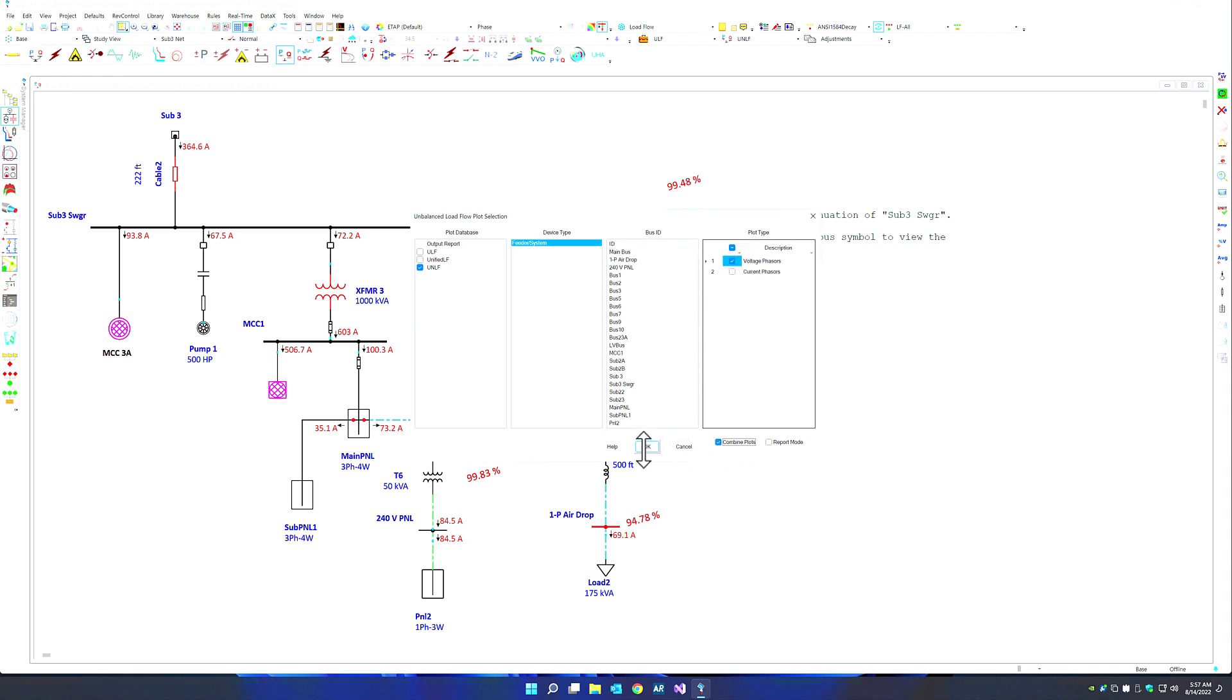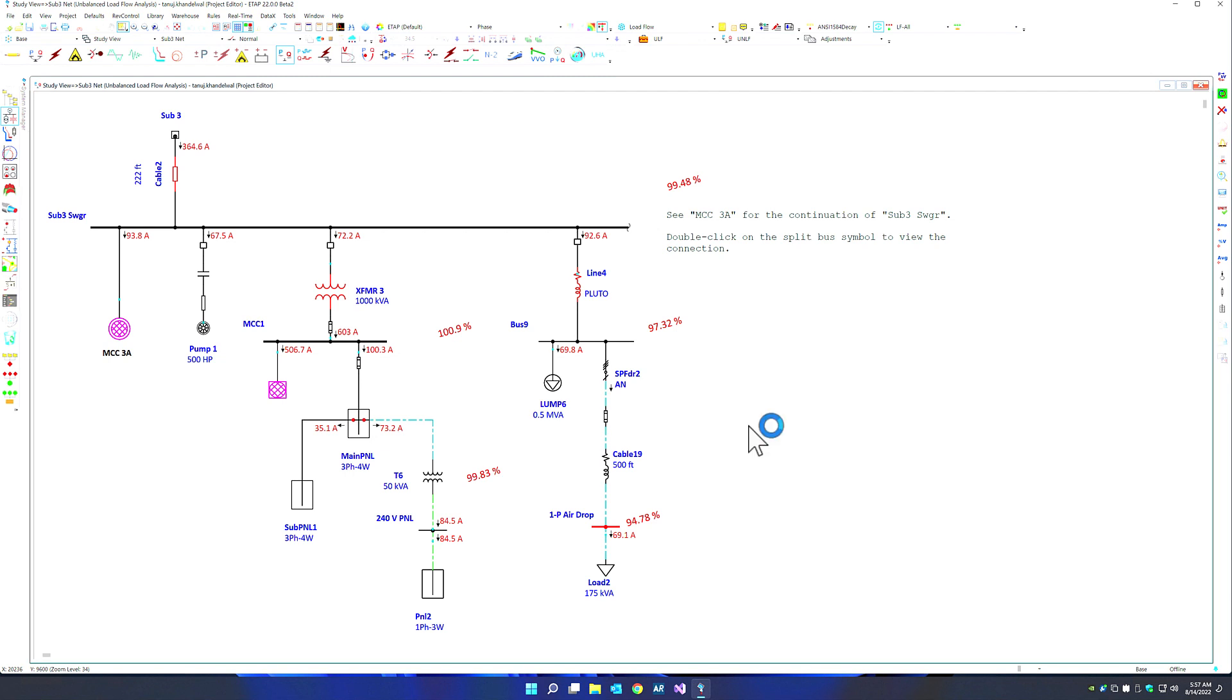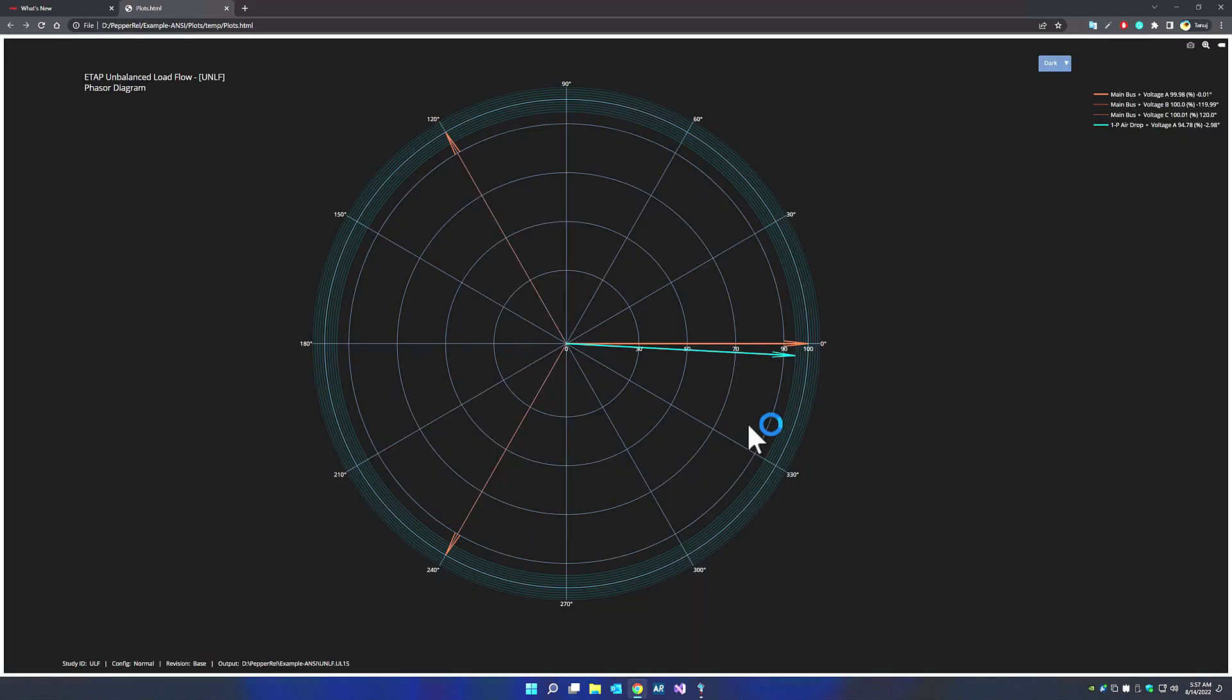Looking at the voltage phasors in a combination, ETAP gives us a very clear indication or a clear picture showing us the phasors as expected for the main bus, which is relatively balanced, and our single-phase vector, which is magnitude and angle for the single-phase bus.